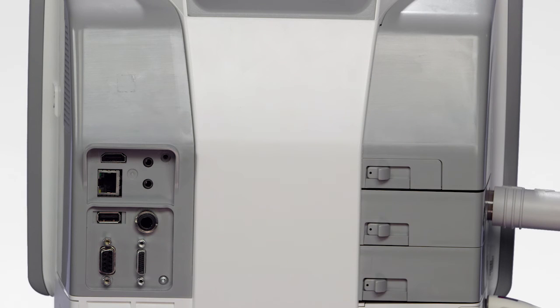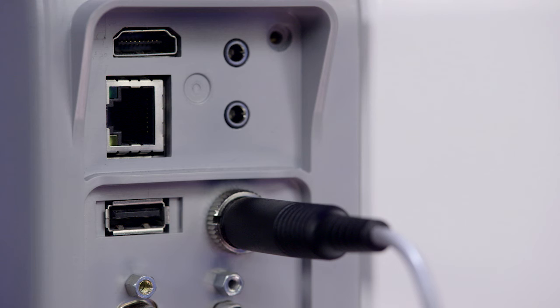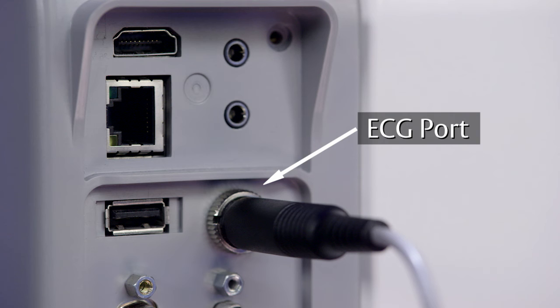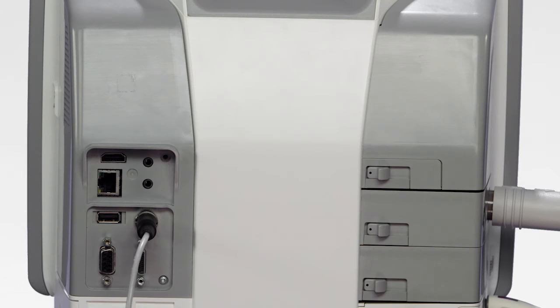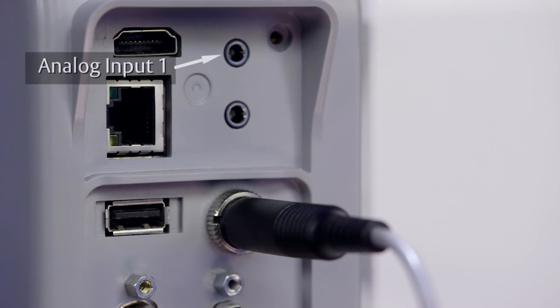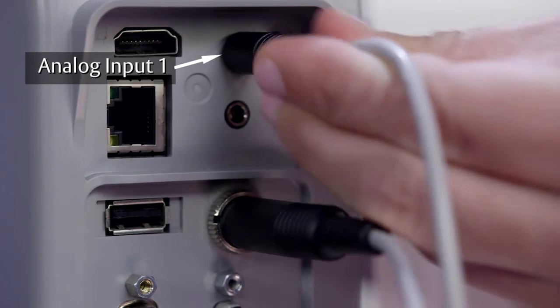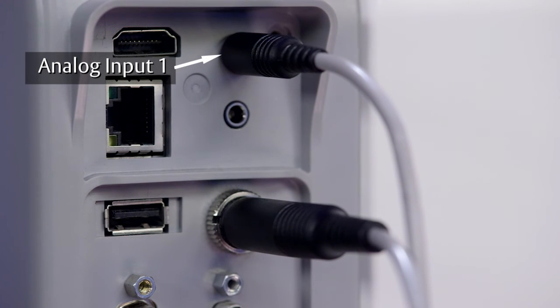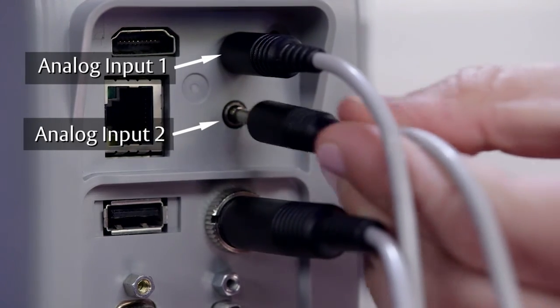representative. To make the proper slave connections to the bedside monitor, connect the ECG cable from the bedside monitor's ECG signal output to the ECG port on the rear panel of the HemoSphere Advanced Monitoring Platform. Next, locate the analog inputs on the back of the HemoSphere Advanced Monitoring Platform. The two ports are interchangeable. For this example, we will connect the MAP cable from the bedside monitor to analog input port 1 and the CVP cable to port 2.